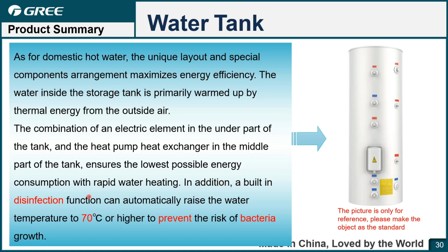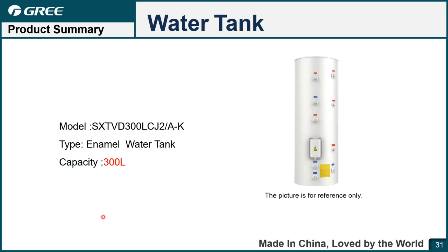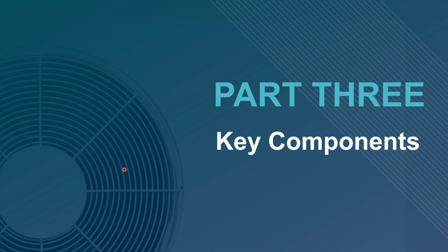And for this water tank, there is a disinfection function. So for long running times, the unit will heat the water to 70 degrees Celsius to kill the bacteria and keep it clean. Currently, the water tank type is enamel water tank. Capacity is 300 liters. And this is the optional one. Maybe you can get another type in the market. It is also possible. Okay, that's the first part about the capacity range.